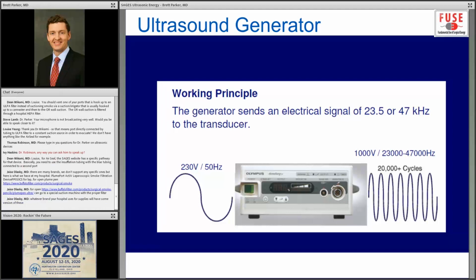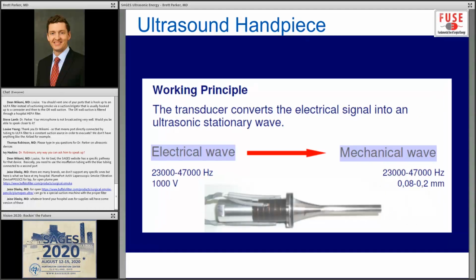And once this energy has been transformed into the higher voltage, it's sent to the handpiece, which is referenced as the transducer. So if you're thinking of some of these devices, they have these silver portions you screw into the back of the handpiece, and inside of those is the transducer, and it looks like this. The transducer's job is to convert electrical signal into mechanical energy or a mechanical wave. And it's kind of neat how it does this.